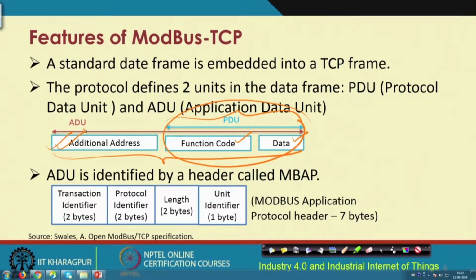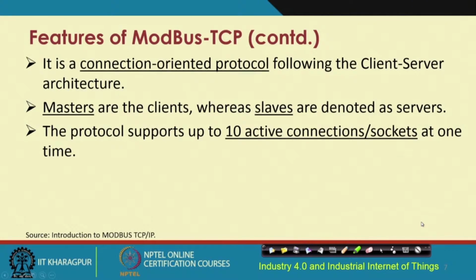So, this ADU, application data unit, has a header known as the MBAP, which stands for Modbus application protocol header, and which is 7 bytes long. The header structure is as shown: 2 bytes of transaction identifier, 2 bytes of protocol identifier, 2 bytes of length and 1 byte of unit identifier. This is the Modbus application protocol header, the MBAP structure. So, we go next and look at the other features.